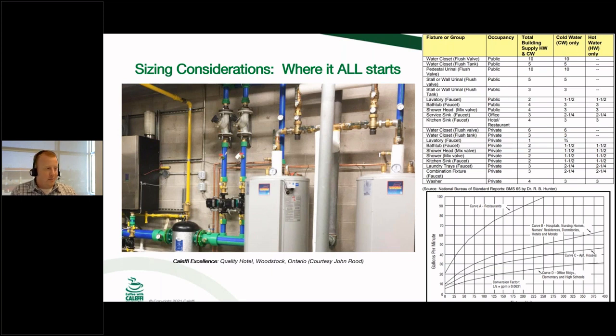Now, here's the other fun part, Hunter's curves are based on data that's very, very old, and we've got a lot lower flow fixtures these days. We're trying to conserve water and energy and all this other fun stuff. So if you're going based on Hunter's curves, chances are you're going to be oversizing your system by quite a bit. And I think a perfect example of this, if you guys were not on for it last month, we had Peter Skinner and Gary Klein on, and they talked exactly about this scenario, where if you're going by the book and sizing it the way you were all taught, chances are you're oversizing it by a huge degree.